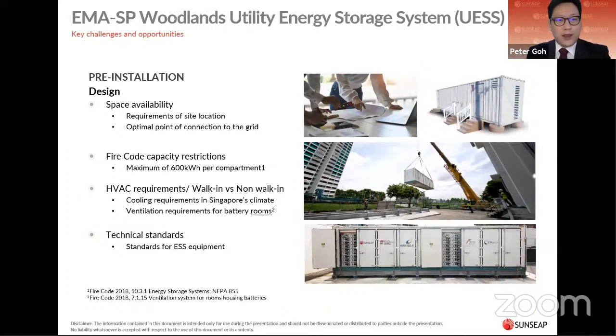Next is regarding the fire rating of the battery container compartments. Our latest fire code introduced a max cap of 600 kilowatt-hours per compartment, which, based on our understanding, references the US standard NFPA 855. But we do know that NFPA allows exceeding this capacity if the system undergoes additional tests and risk analysis. For such safety concerns, we can refer not only to US standards and the local fire code, but more recently, Singapore's TR77 standard for guidance.